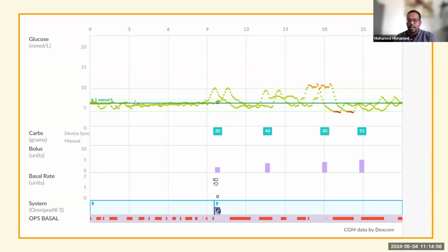And these are all alarms you can set in the system. So you can set your target between 4 and 11. If the blood glucose is trending below 4, the basal insulin stops. Unless you give insulin to override that, the pump will not give any insulin until blood glucose stabilizes again, and then it restarts giving insulin. I hope this answers the question.